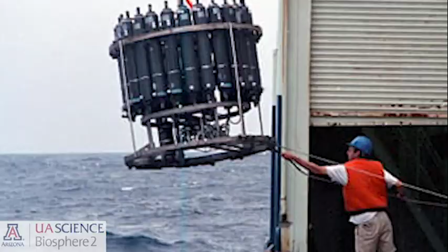So in class we talked about CTD, or conductivity temperature depth profiling. On the oceanographic vessel that we would have gone on in Southern California, we would have gotten to see one of these, what we call a rosette. A rosette has one of these CTD instruments on the bottom of this big metal ring, and in that metal ring are also water bottles. So we can lower it slowly to create a depth profile of temperature, dissolved oxygen, and conductivity, and a number of other specific parameters that can be adjusted depending on research interests. And we can identify parts of that profile that are of interest for whatever our research question is.